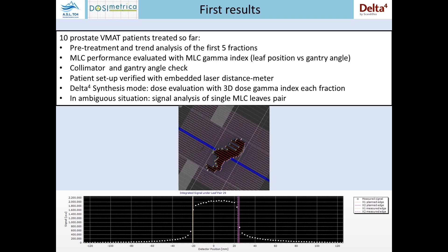For each patient we have the pre-treatment result and the trend analysis for the first five fractions. On these patients we made MLC performance evaluation using the MLC gamma index, a specific parameter provided by the Discover software. We also check daily the collimator angle, the gantry angle, the patient setup using the embedded laser distance meter. And since we were working in Delta4 Synthesis mode, every day a dose evaluation with a 3D dose gamma index was performed.